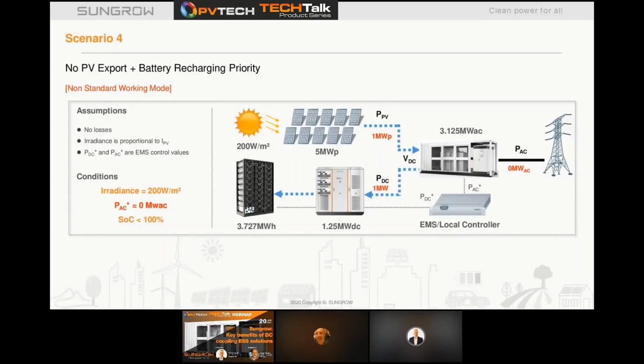Another non-standard scenario, during the day, grid zero export. Again, these are the periods where we get the curtailment. There is only 1 megawatt DC coming from the solar array. State of charge of the battery is low. The battery charges as a priority. The DC-DC converter is taking over the MPPT tracking and charging the battery.